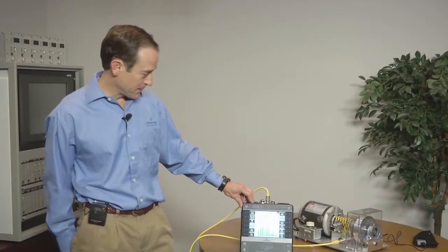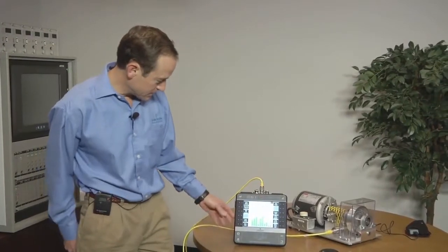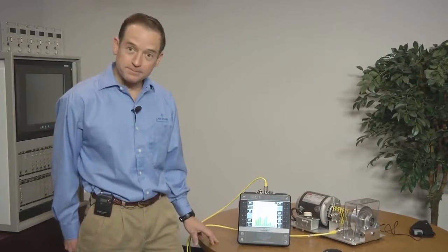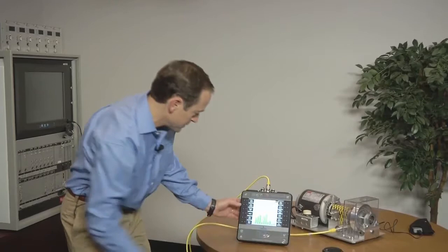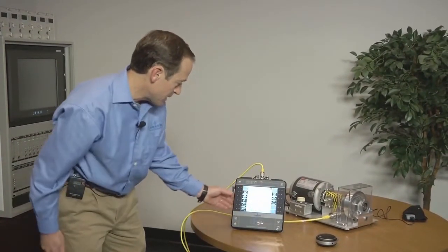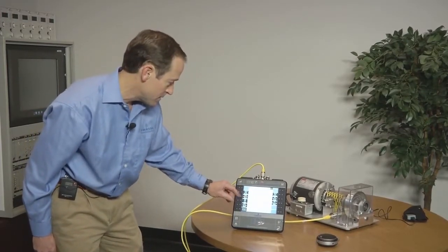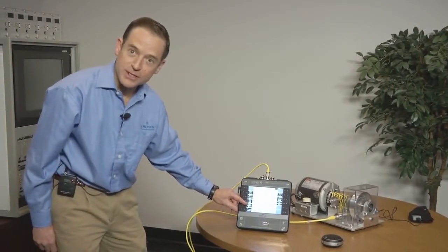Demonstration number 3 is to show immediate problem notification while in route mode. The setup on the 2140 is to first go to fan inboard vertical. And then the specific setup is a little bit different, so go to Alt, User Setup, and in User Setup we want to turn Auto Advance to 0, and we want to change Data Storage Mode to Save All Data.